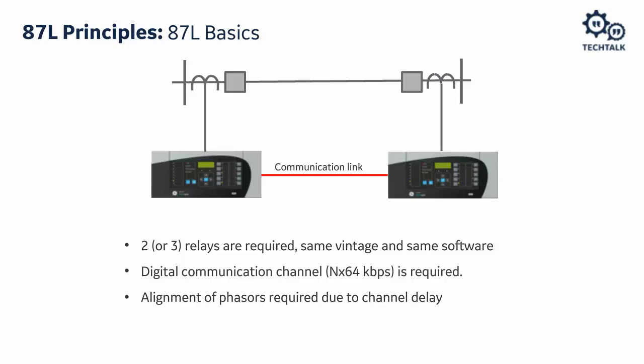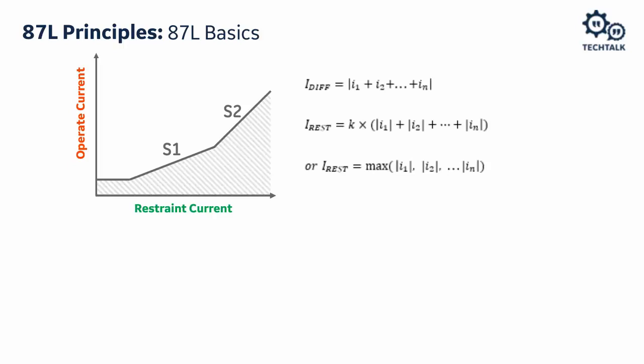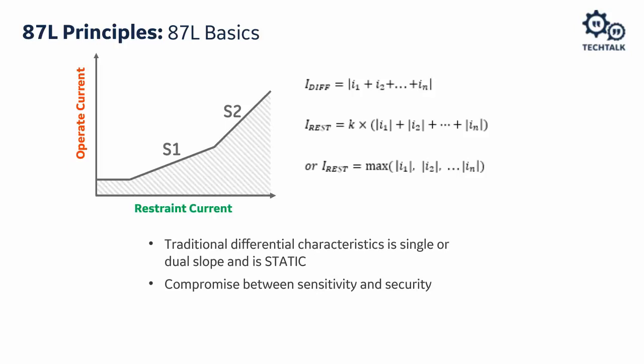We need to align phasors — this is the most difficult part of the differential, technically speaking. Looking at the traditional percent differential characteristic: there is a minimum pickup zone, slope one and slope two zones, representing the traditional operate and restrained differential characteristic. The differential is the sum of all zone input currents. For restraint we have two approaches: the sum of absolute values of all zone input currents, or the maximum of zone input currents. It's a compromise between sensitivity and security.